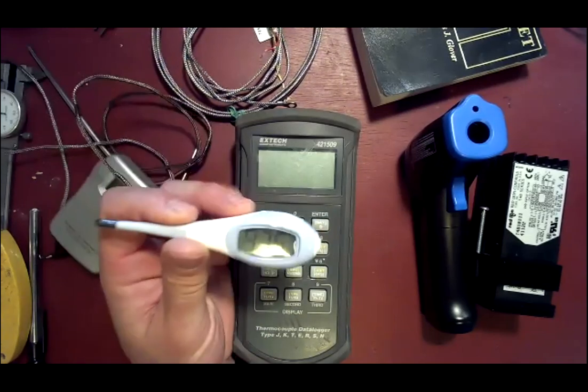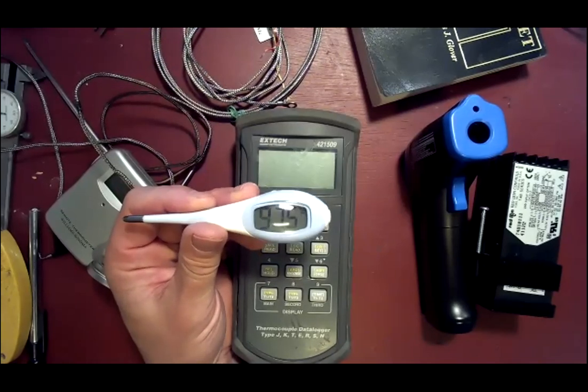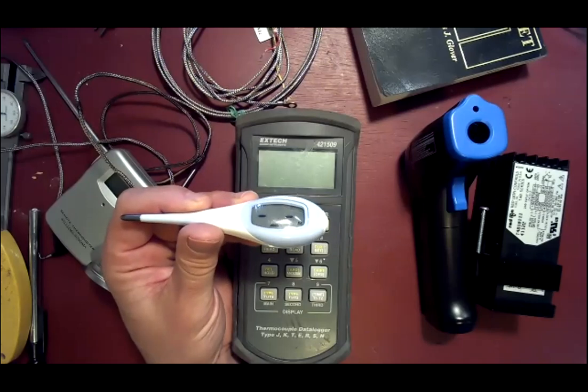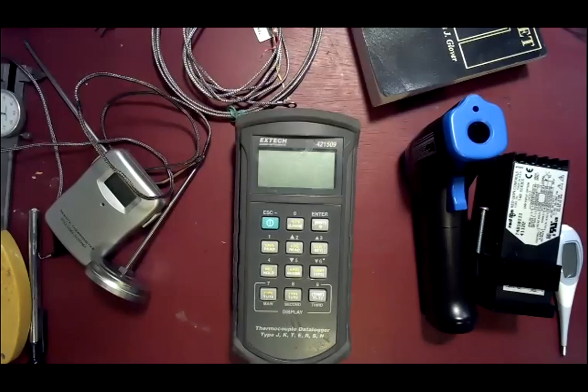So this demonstrates three key features of accurate temperature measurement. Number one, it was fully immersed in the environment where it needed to measure the temperature. It wasn't on the surface, it wasn't nearby, it was fully immersed. That means the sensor probe was fully immersed and is going to be accurate to the center of whatever you're measuring.